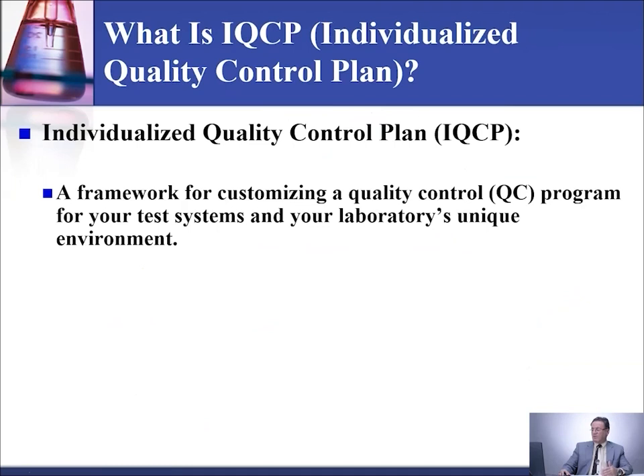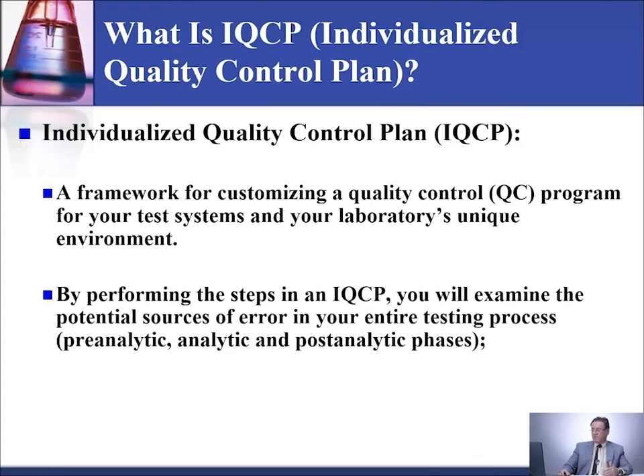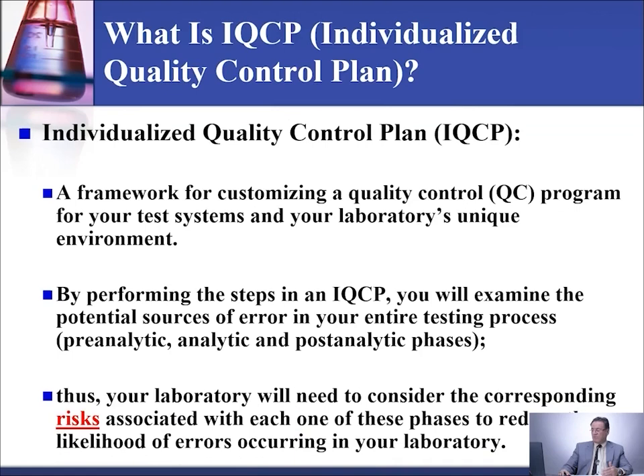Now, what is the definition of an IQCP? It is a framework for customizing a quality control program for your test systems and your laboratory's unique environment. By performing the steps in an IQCP, you will examine the potential sources of error in your entire testing process — pre-analytical, analytical, and post-analytical phases. Your laboratory will need to consider the corresponding risks associated with each of these phases to reduce the likelihood of error occurring.